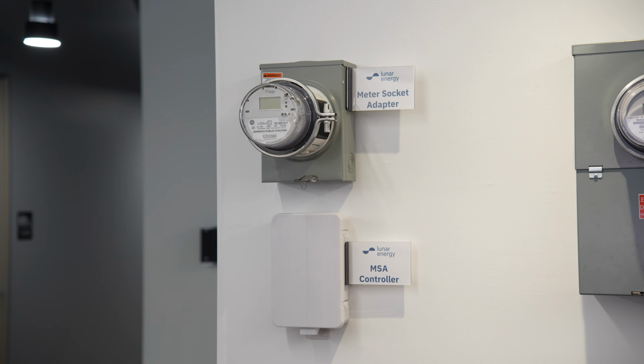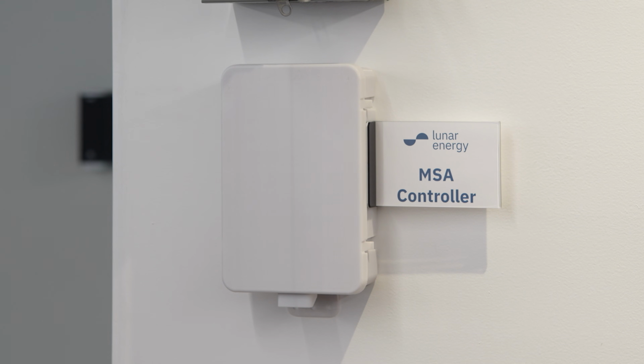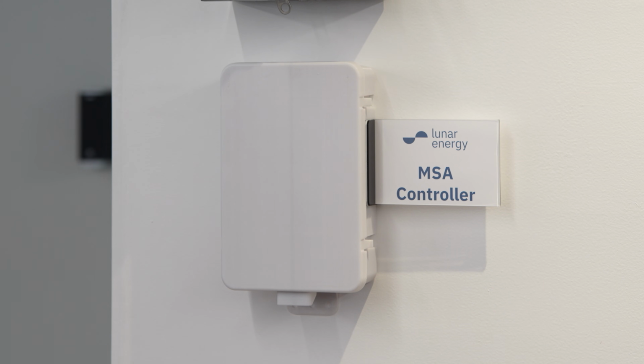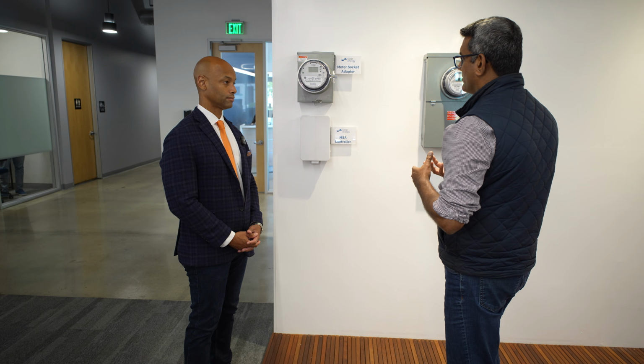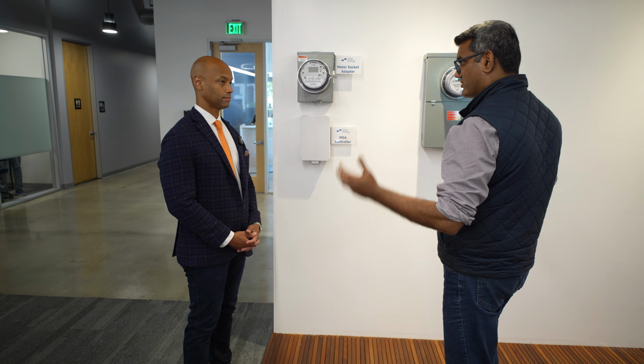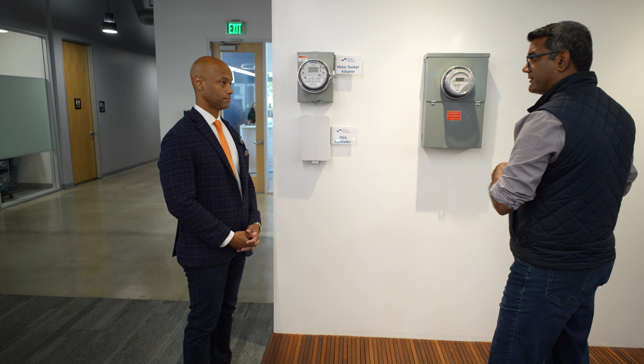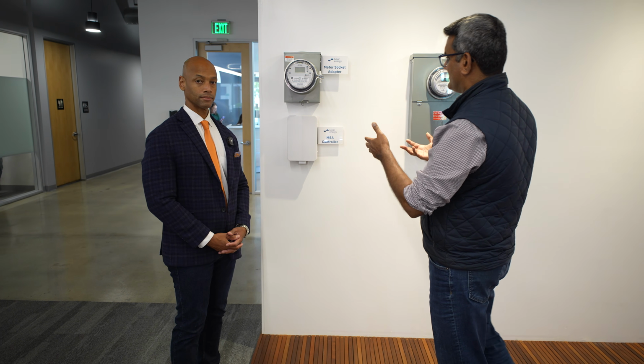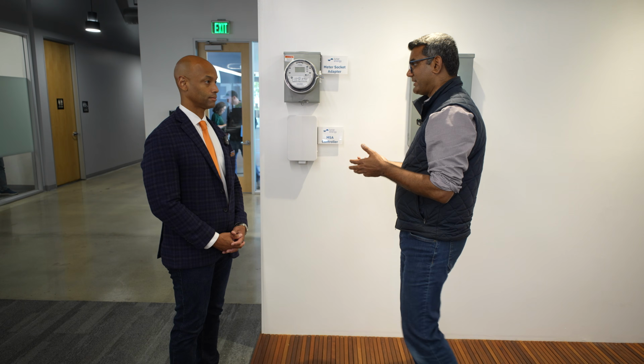In PG&E territory in California, we'll be offering this product to installers, who can choose to install a Lunar bridge or the combination of a Connect DER meter socket with a Lunar meter socket controller. With this combination, they'll be able to avoid any and all load relocation. This is especially a problem in California, because Californian homes have this unique configuration of a meter-main electrical panel, which requires every load to be relocated if such a panel exists. So this avoids that unnecessary load relocation and can save installers $3,000 to $4,000, and homeowners the headache of a long installation time.